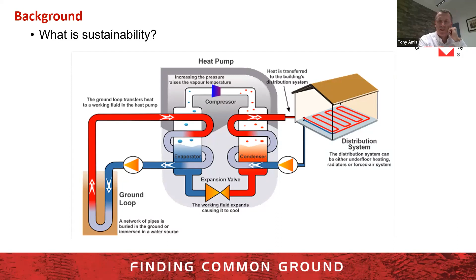With a ground source heat pump solution, it all hinges around the second law of thermodynamics: heat will always move to a colder place. The beauty of the ground source heat pump is that the ground we're drilling foundations into, once you get below about 10 feet, the ground temperature remains pretty constant year round. Here in New York, we've seen it range from 55 to 60 degrees Fahrenheit. So in summertime, when trying to provide cooling to a building, we've got that nice cool ground to provide a cooling solution.